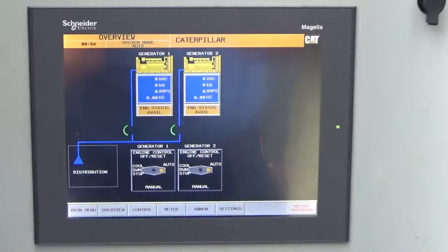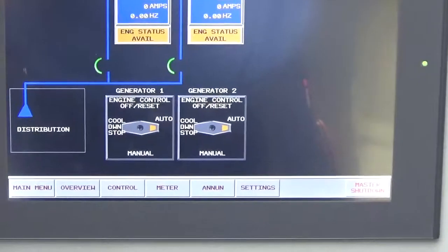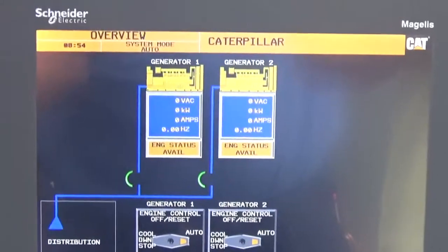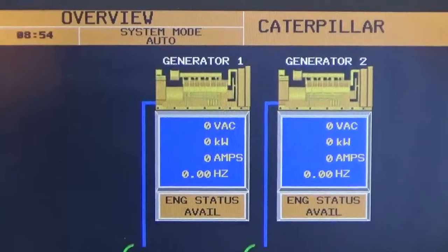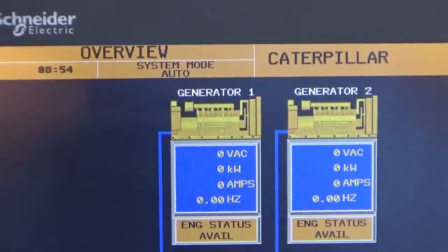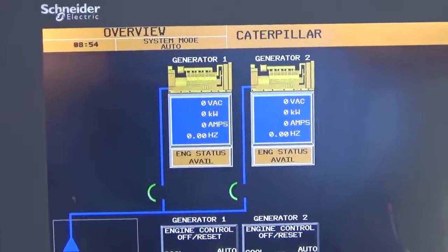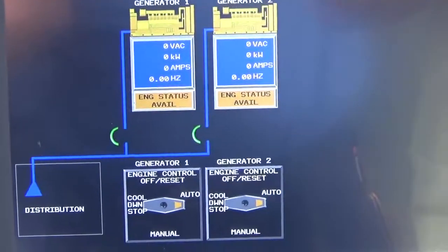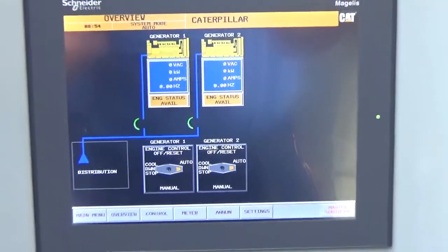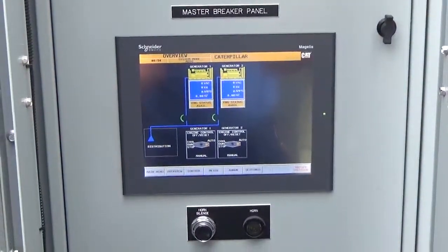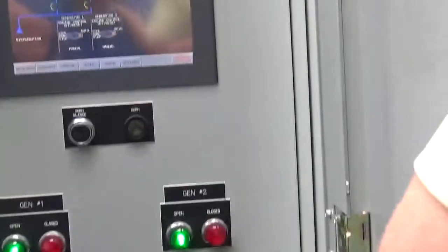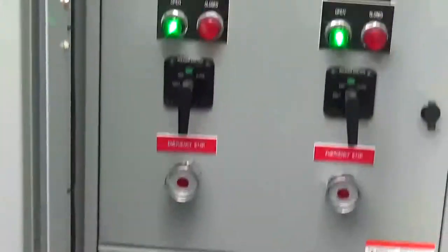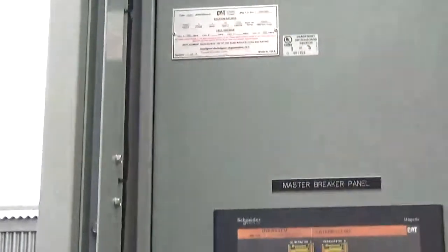On Friday, we got a pre-alarm at like 2 p.m., after we rolled the switches and ran it. An hour later, the pre-alarm came in. We went through and acknowledged it. Like you said, we were kind of running blind. It just said pre-alarm. You didn't have any flashing lights or blinking lights? Over here, I'll show you which one was blinking. So we came up and then cleared it here. We had to go downstairs and clear it at 2 other locations. Everything cleared here. And then it came back Monday morning, when I came on early in the shift.